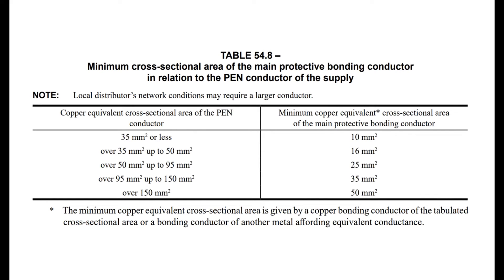Table 54.8 gives the following examples that you can select without calculation. And in a domestic environment, where most installations use 25mm squared meter tails, the main protective bonding conductor would be 10mm squared. And this is what people generally stick to.